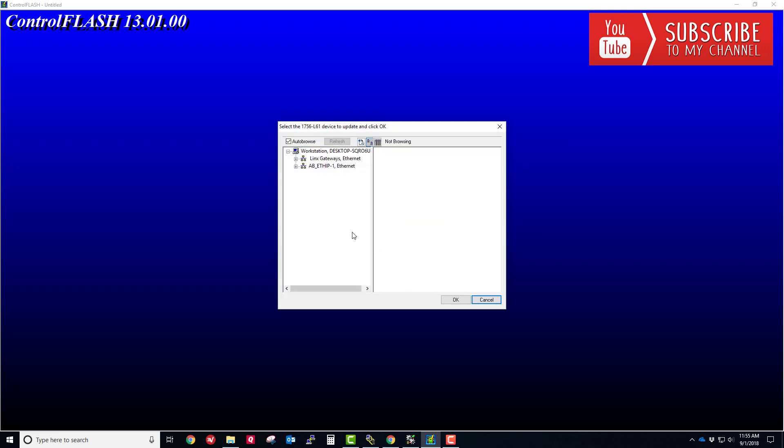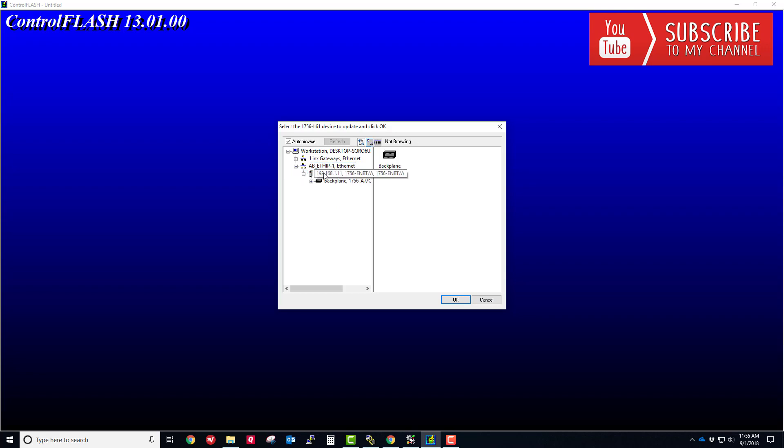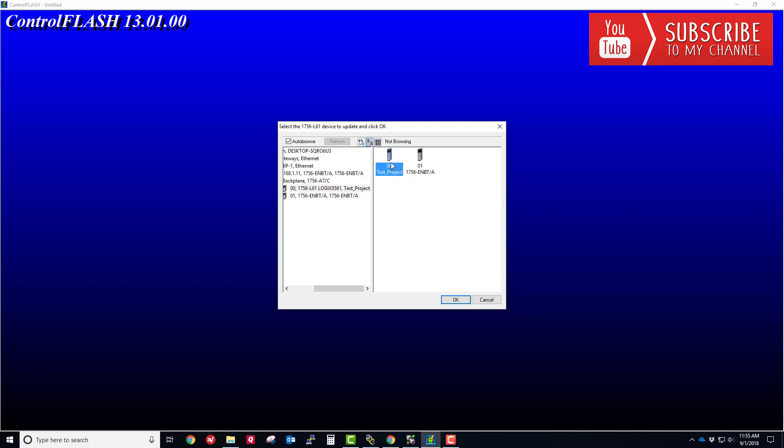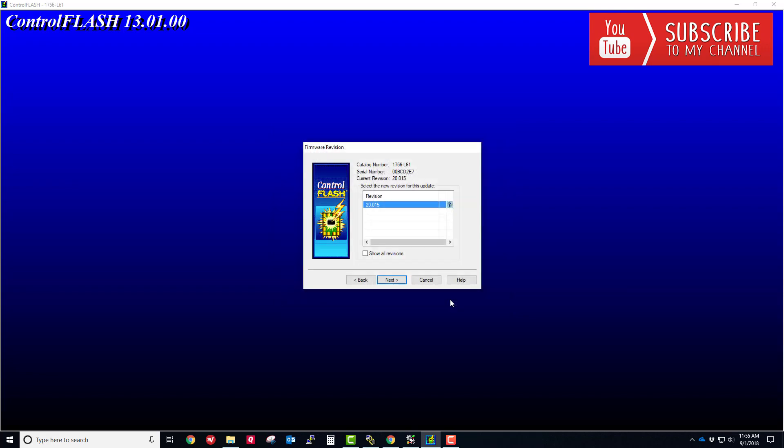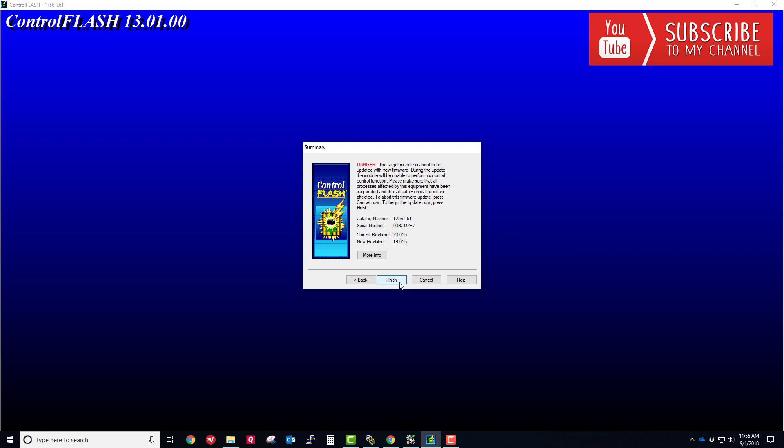Now we need to browse using this RS Who window to the physical processor. We're going to drill through the ethernet bridge through the backplane, and then select the processor residing in slot number zero, which has something called test project right now. I'm going to click OK. You can see I am running version 20 on this machine. However, if I check this box to show all the revisions, there is the version 19 that we just installed. I'm going to choose that and choose Next.